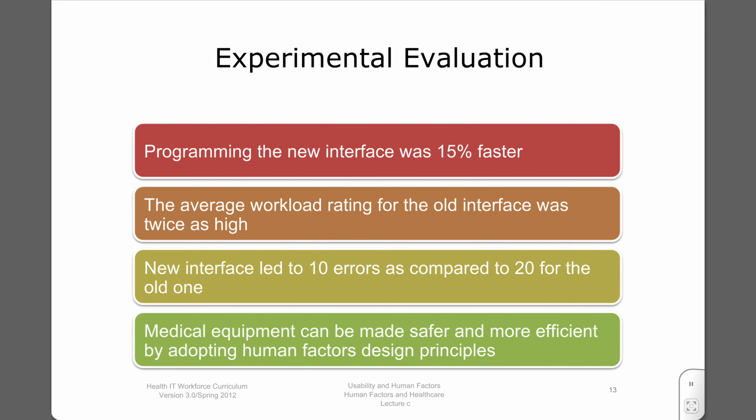They conducted a cognitive study with 12 nurses comparing simulations of the old and new interface. They found that programming the new interface was 15% faster. The average workload rating for the old interface was twice as high. The new interface led to 10 errors as compared to 20 for the old one. This is a compelling demonstration that medical equipment can be made safer and more efficient by adopting sound human factors design principles.